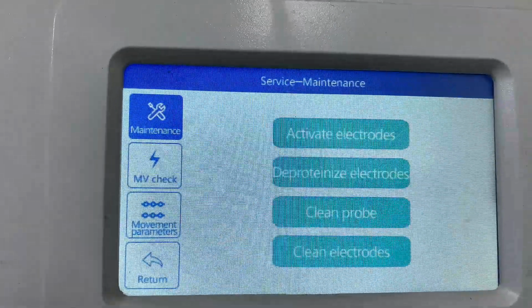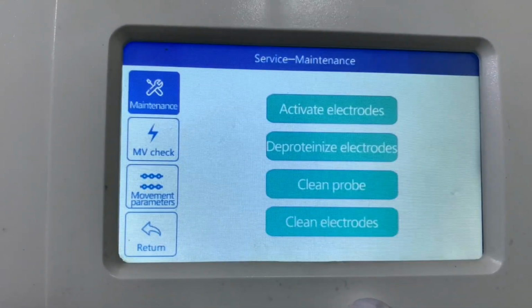After clicking service, you'll see the maintenance. Maintenance has been highlighted or it is showing blue. Then you'll see options to activate electrode, deproteinize, clean probe and clean electrode. This activation of electrode has already been done while the machine was coming up. Then for the maintenance, you are going to deproteinize, clean probe and also clean your electrodes.